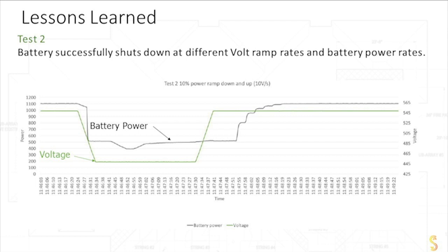And what you'll notice too, you might ask, why doesn't the battery power go to 0? Isn't that what it's supposed to do? Right, you would think so, but these are auxiliary loads. Remember those auxiliary loads? That's where that 500 watts on this graph is going. So the battery has been shut off. You can see that in the dramatic spike in the jump. When the green line comes down, the dark line does too. That's the battery turning off. But we still see some residual load coming into the battery because that's the auxiliary. And you see it fluctuates too. Pumps, or if there's HVAC and pumps and motors and controls and fire suppression, they might turn on and off at different times for different reasons.